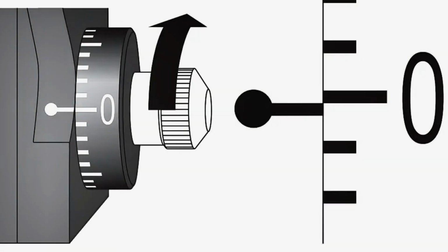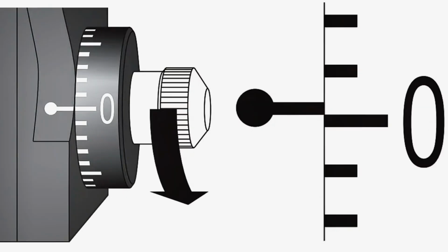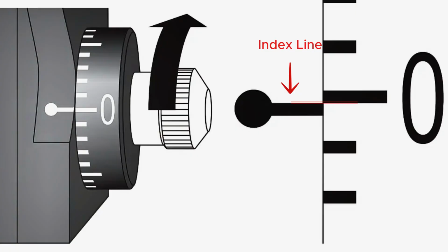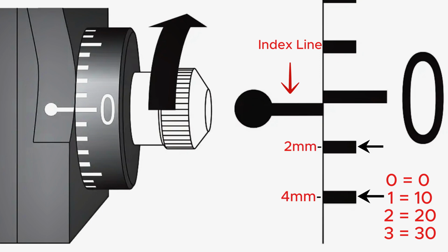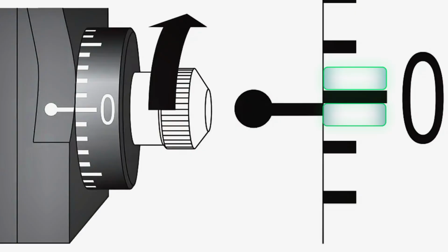This image shows exactly where the feeler arm should begin to drop toward the patient and where it should return toward the operator. Notice how, in this example, the bottom edge of the tonometer index line aligns with the top of the dial increment. In the opposite direction, the top edge of the index line aligns with the bottom of the dial increment. Each whole number on the dial represents 10 millimeters of mercury, and each small line represents 2 millimeters of mercury. Any movement that occurs outside of that half millimeter range indicates the tonometer is out of calibration. As shown here, the feeler arm should drop within the green highlighted area. If it falls outside this range, the tonometer requires calibration.